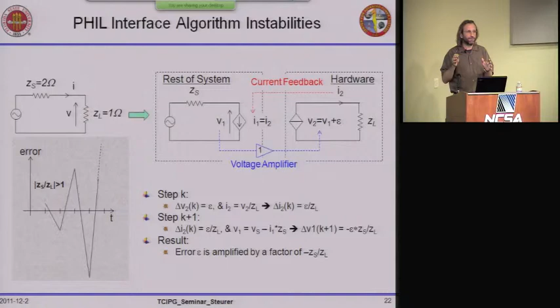However, if you go through this evaluation with some error in the signal, and acknowledge that there's at least one time step, if not a longer delay, between what you send out and what comes back, you see that this particular case is completely unstable. If it were the other way around, with 1 ohm and 2 ohm swapped, it's actually stable. So understanding the interface is essential to conducting real power hardware in the loop simulations.